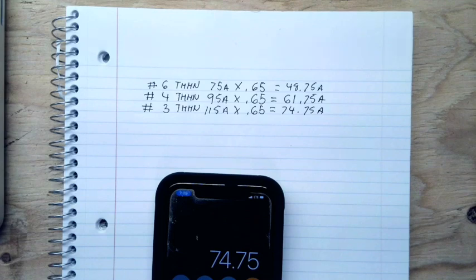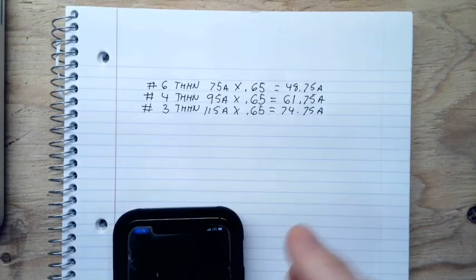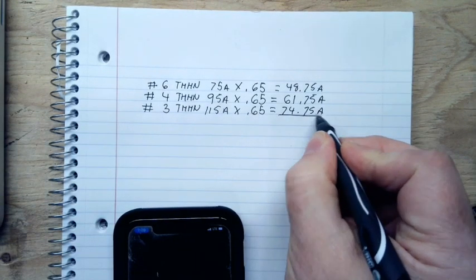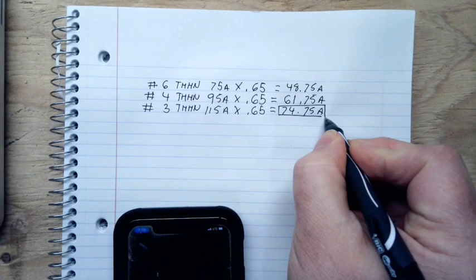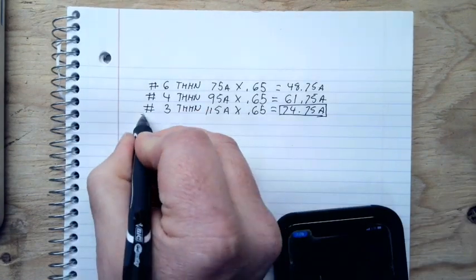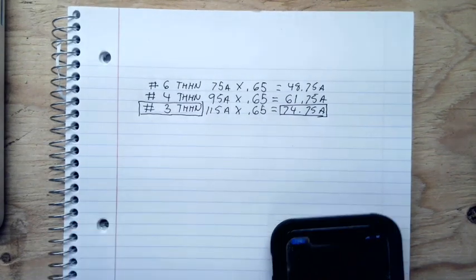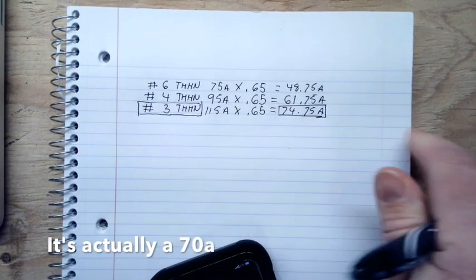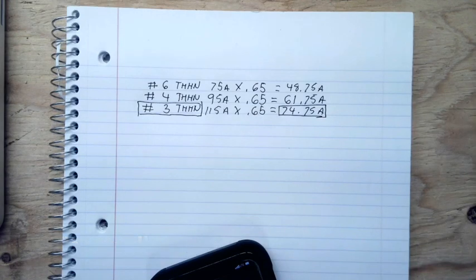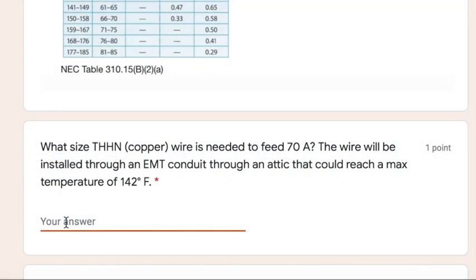And I think with that, we're going to be good enough, right? Because I'm looking for 70 amps. So that 74.75 amps meets our requirement. So we will need a number 3, THHN, to feed a 70 amp circuit. So now when I come over here, I'm going to write that like this. I'm going to say number 3, THHN, and we're dealing with copper. So that's my answer.